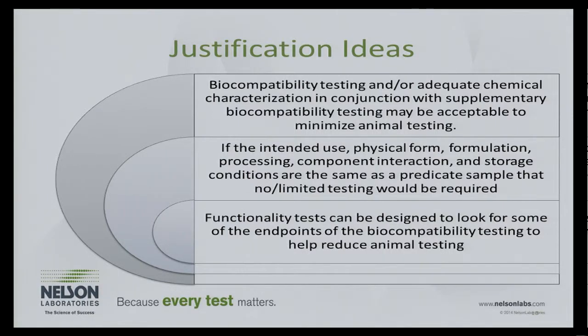We can put implantation data. We can put systemic toxicity data in functionality tests. If you call me, I'll give you my protocol. I won't even run the tests. I'll let you have what we look for, and so you can put it in your functionality protocol, so therefore we can use that data to justify out of the testing later on. As long as the product doesn't change, then we can use that data, okay?